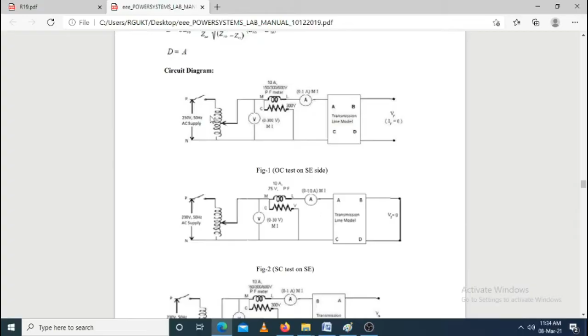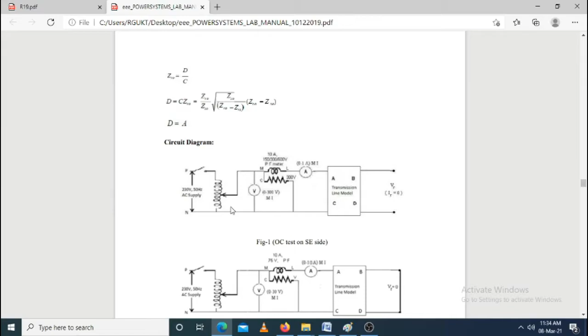For the transmission line ABCD parameter, using the ABCD transmission line model, we apply the rated voltage on the primary side, while the secondary side is open circuited.